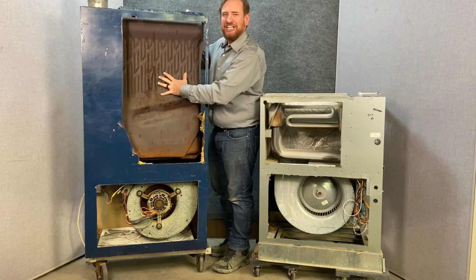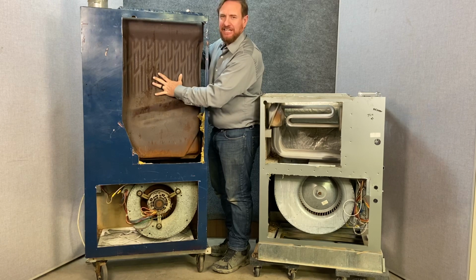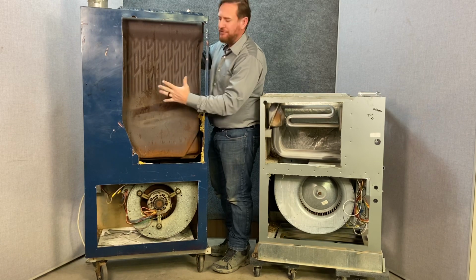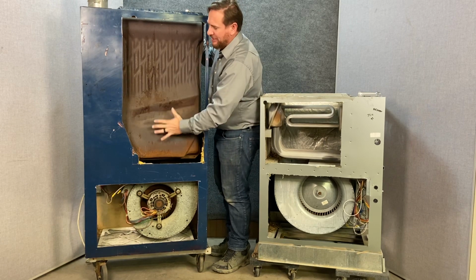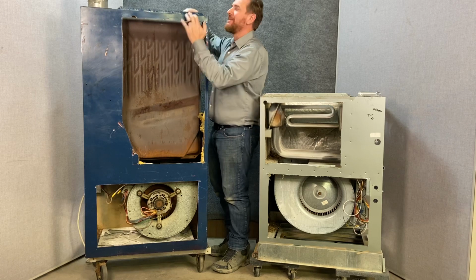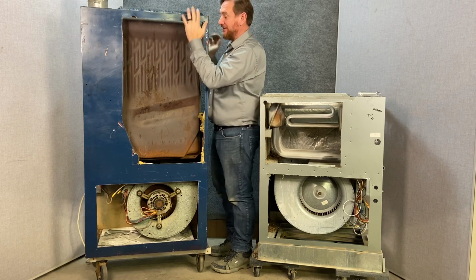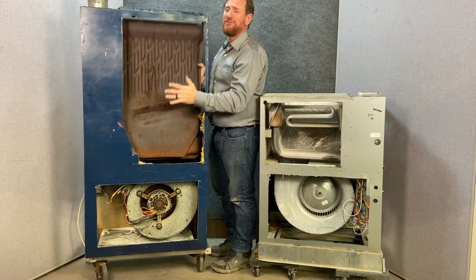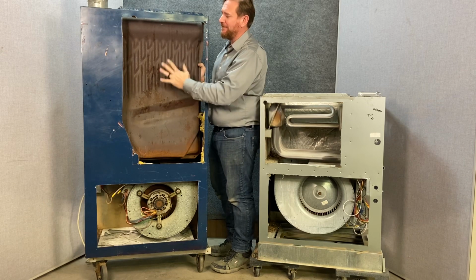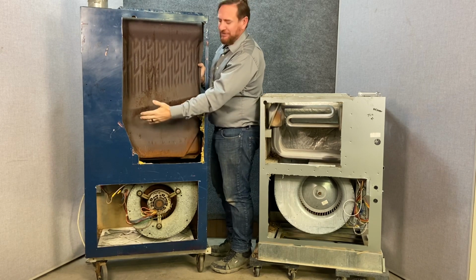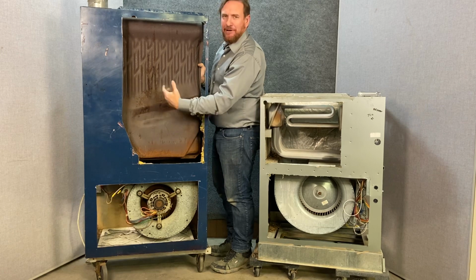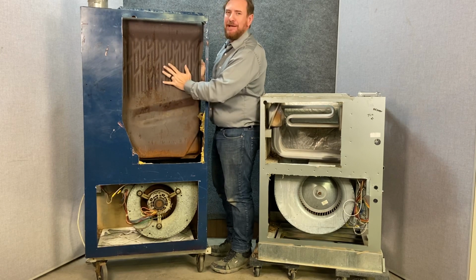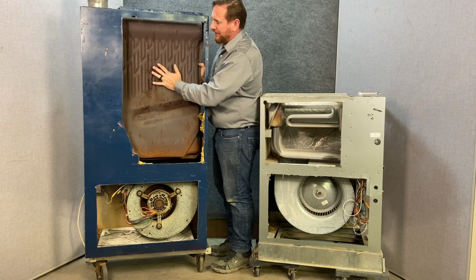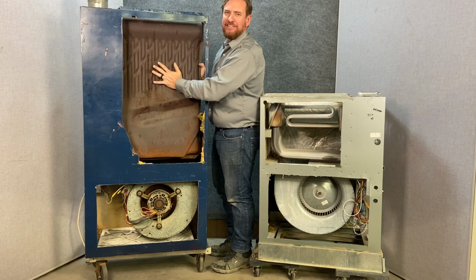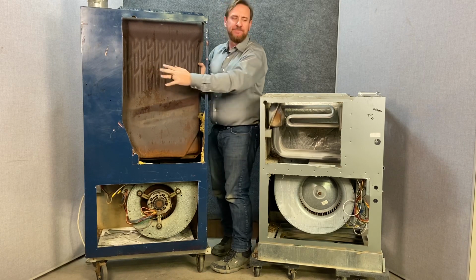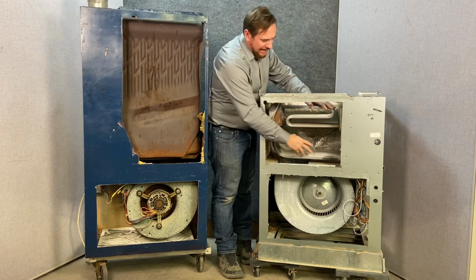Now, when this heat exchanger cracked, it would allow the combustion gases, the carbon monoxide, all these other fumes to come out of the heat exchanger into the blower stream and actually poison the customer in their house. So these heat exchangers leaking was a huge issue, and we were always checking them. Many ways of checking them. We would send a light inside, a camera, mirrors. There's many methods of checking these, but these old things would crack and leak carbon monoxide, and it was a huge, huge safety issue.